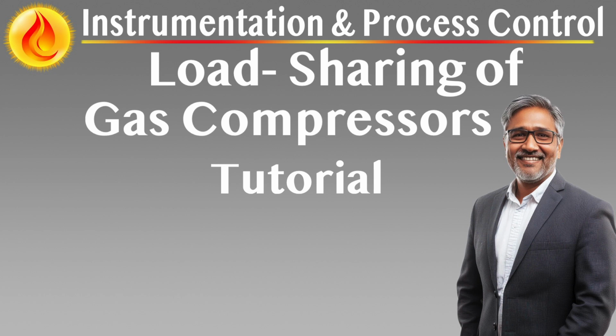Dual algorithm response logic. POC employs a two-pronged control logic structure. 1. One-sided PI response, proportional plus integral, monitors the deviation of the pressure or flow variable from a predefined override set point. This set point can be an absolute threshold or an offset from the primary control set point, only activated when deviation exceeds in the defined critical direction.